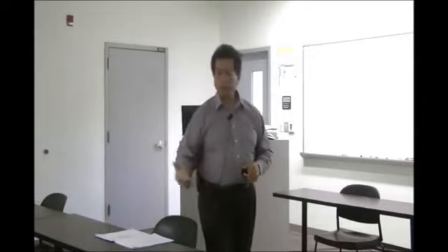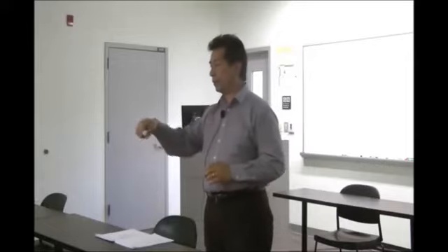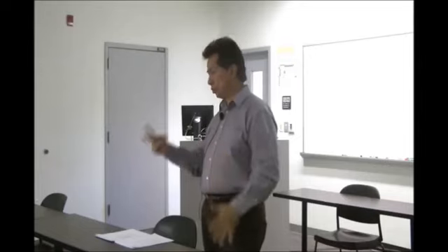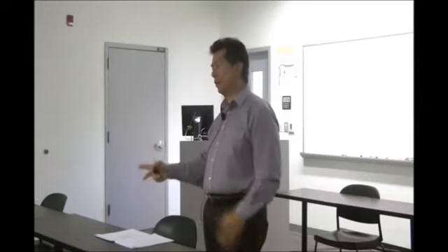Okay? And can the existing control system support these upgrades? Case in point, I had a small renovation. It's that area you walked by in the 1360 area at the Hayden. Yeah. That's going pretty quick, isn't it? Okay. Well, I'm talking about life safety. That's about, I don't know, 4 times the size of this room here. But when we were going through the renovation, we found out that our annunciation panels for our evacuation systems, strobes and evacuation horns, were overtaxed with this room. We had to install 2 more for this room to make it code compliant, part of the renovation.